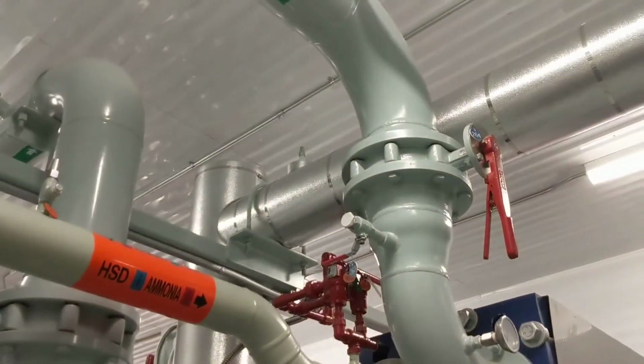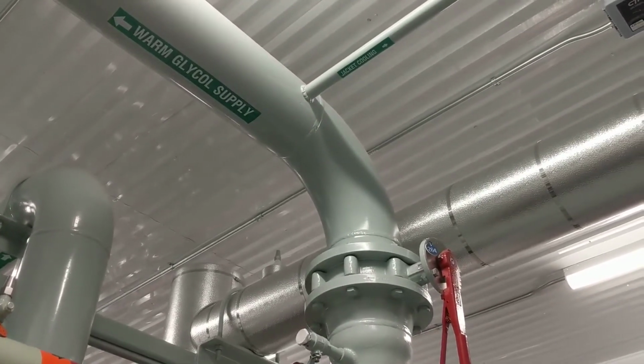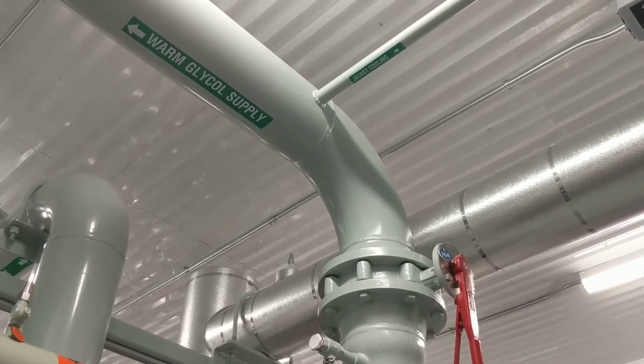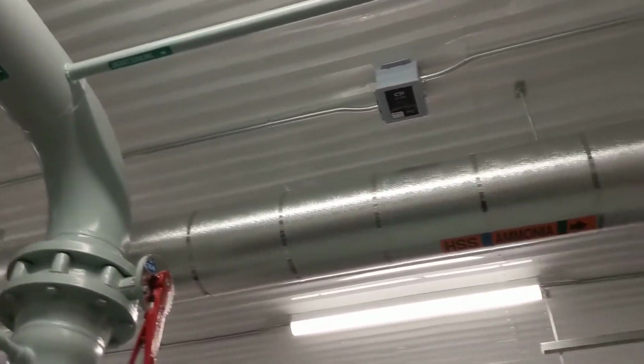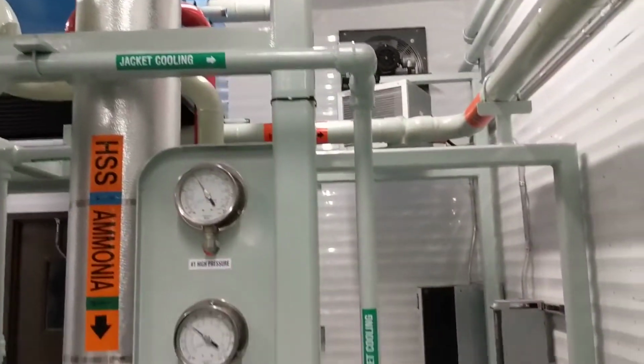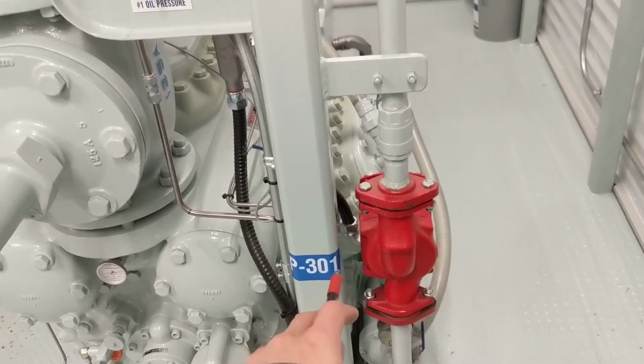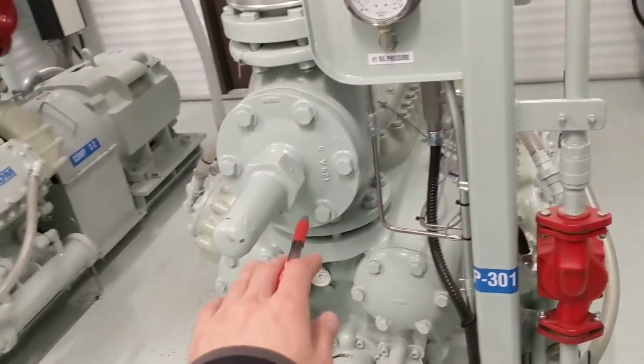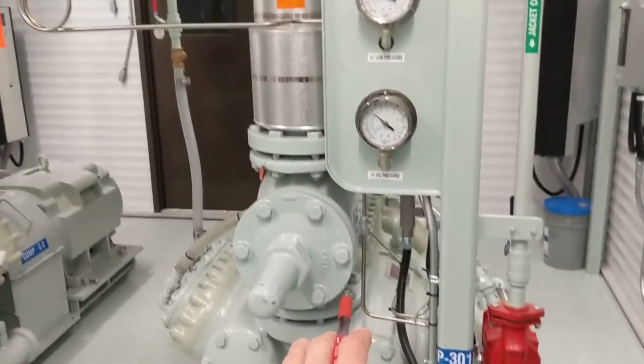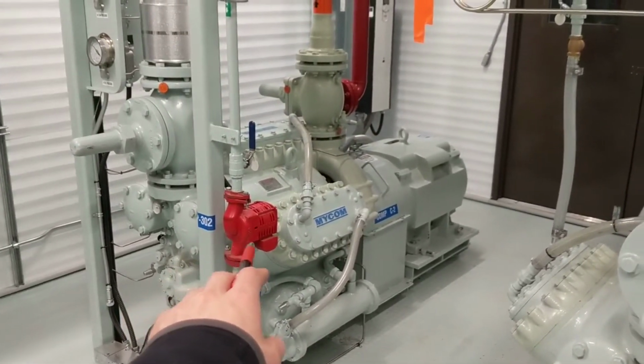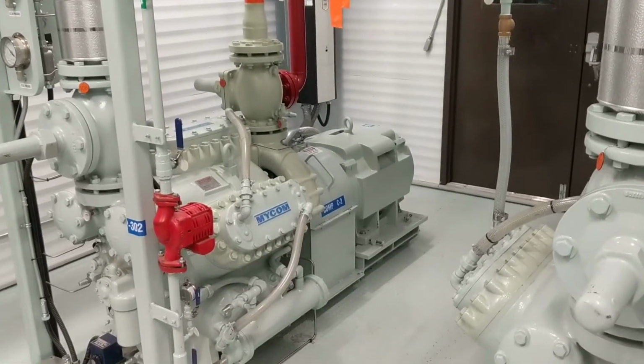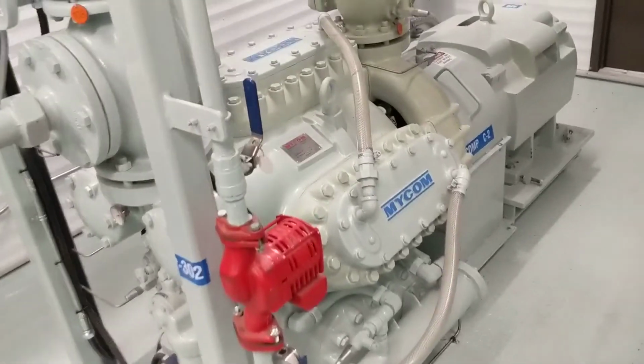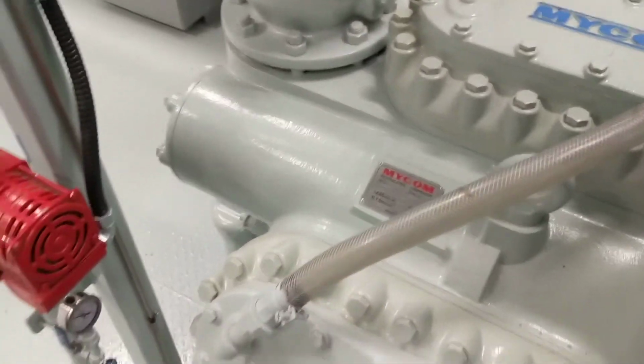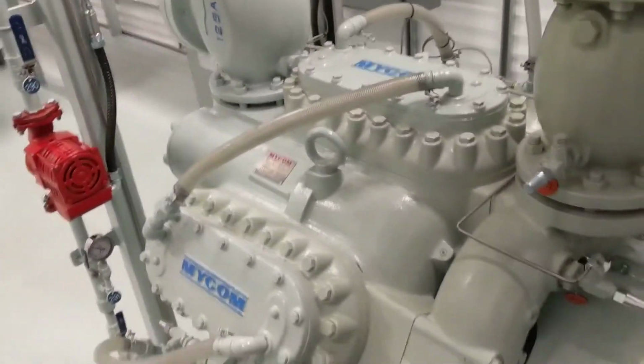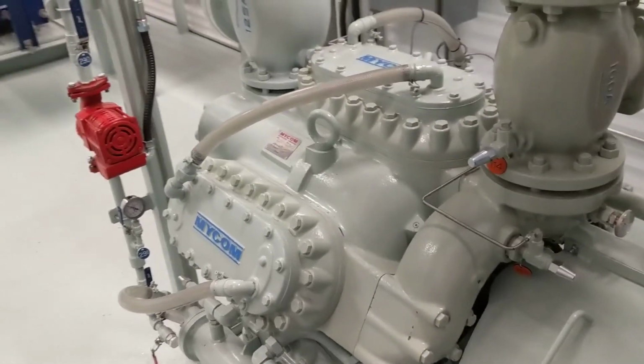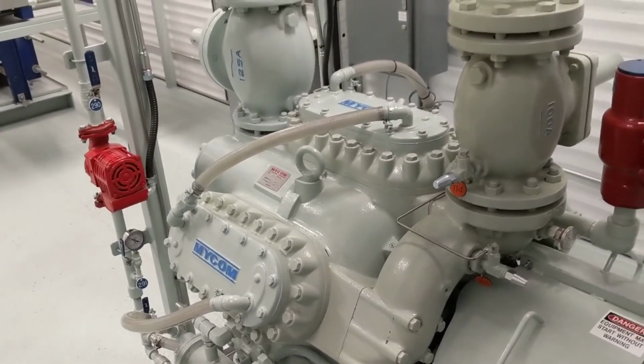The other thing that this glycol is doing is it's being used for the cooling jackets. So you'll see that little pipe up there where it's branching off and coming down here to the cooling jacket. And so this P103, there's P301, the little red pump here that circulates the glycol over compressor 1, and P302 over there circulates the glycol through compressor 2 heads. And so what these do is these cool the compressor heads. So if you think of that like the radiator in your car being used to cool your engine, this glycol loop on the compressors cools the compressors.